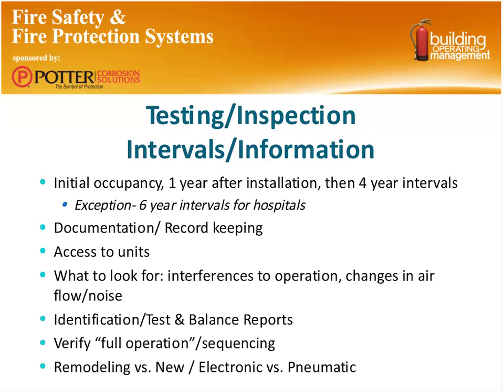Access to the units, this is a problem we run into. We are also a mechanical contractor, and I've got to say that there are a lot of systems where those dampers are either trapped, as in you can't physically reach them, or the access ports were never cut in, and you can see the motor operator from the outside of the duct, but you can't get inside to take a look at it. And when we say take a look at it, this is beyond just a little 6x6 access port cut in the duct. It should be big enough that a person can physically look inside of it and truly inspect the condition of that damper and verify that it's actually operating. So I guess the point of that is make sure they're sized properly.